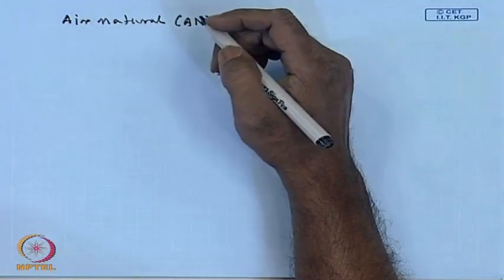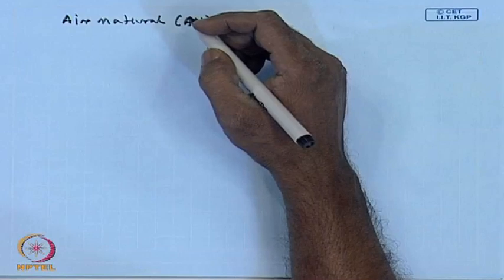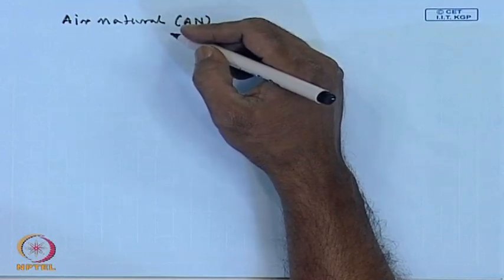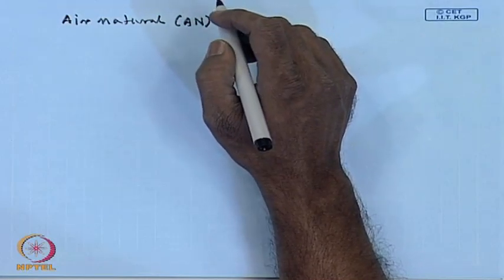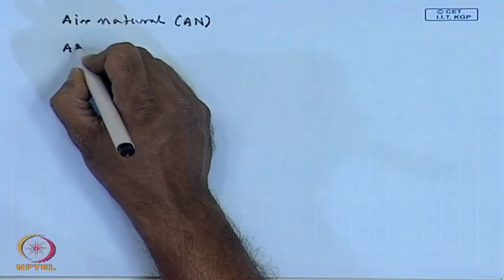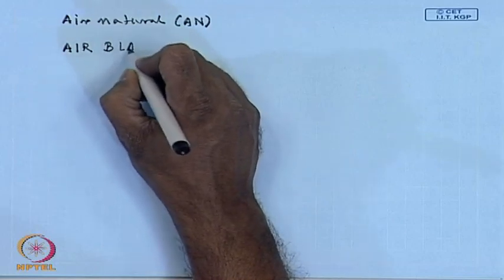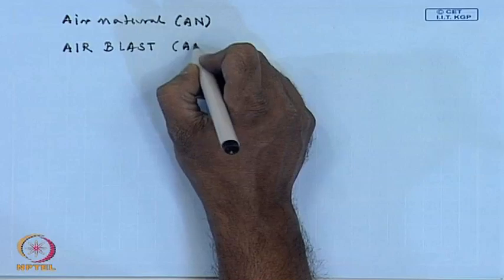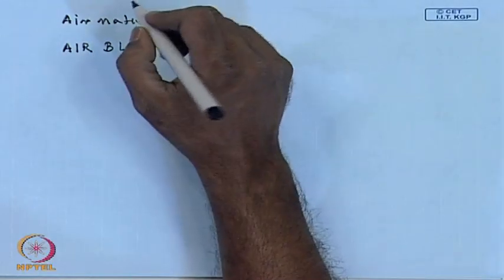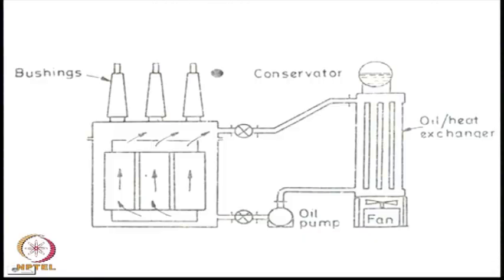On a slightly higher rated transformer, natural air circulation may not be sufficient to prevent temperature rise, in which case the transformer may be cooled using a fan. This is called air blast cooling. Except in very special applications where using a cooling medium is hazardous, these are used only for small rated transformers. For a large majority of transformers, they are usually oil immersed and the transformer oil works as a medium of cooling.